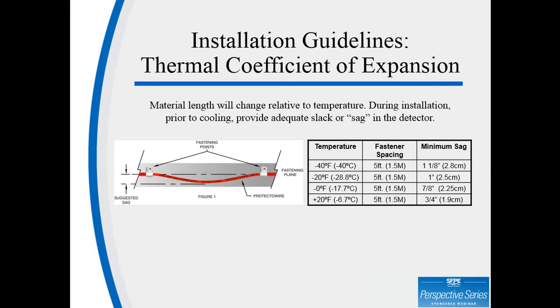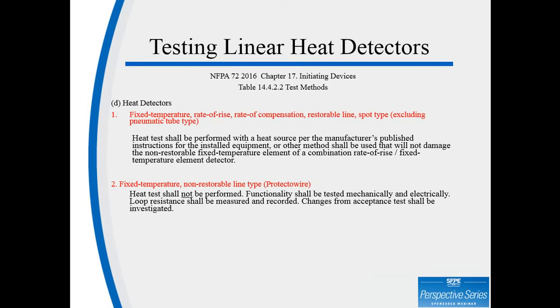Testing digital linear heat detectors. NFPA 72 is very clear on how to test restorable detectors and non-restorable detectors. And the basic difference is, with fixed temperature restorable or rate of rise, a heat test shall be performed on each and every detector, which can be very laborious and time consuming. With fixed temperature non-restorable line type, Protectowire or digital LHD, the heat test does not have to be performed.